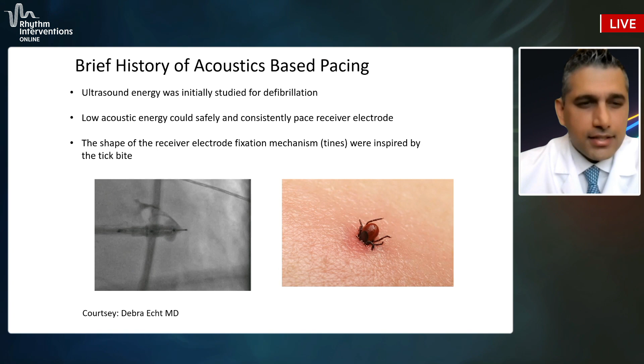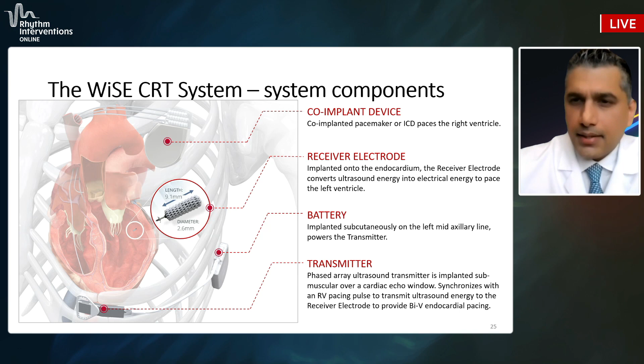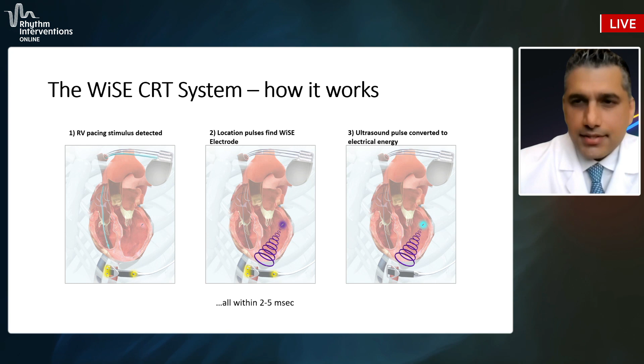So the WiSE CRT system needs a co-implant device, such as an ICD or pacemaker RV lead, and a receiver electrode, which is very small, maybe the size of a grain of rice, with a length of 9.1 millimeters and diameter of 2.6. It has a battery which goes in the left mid-axillary line, very much like a sub-Q ICD, and a transmitter which has an ultrasound crystal to send the ultrasound signals to the receiver. The way it works is that the WiSE CRT system first senses the pacing stimulus, and that triggers the crystal in the transmitter to send ultrasound energy to the receiver electrode. This electrode converts the ultrasound energy back into electrical energy, and it paces the LV endocardium. This whole process takes around 2 to 5 milliseconds.